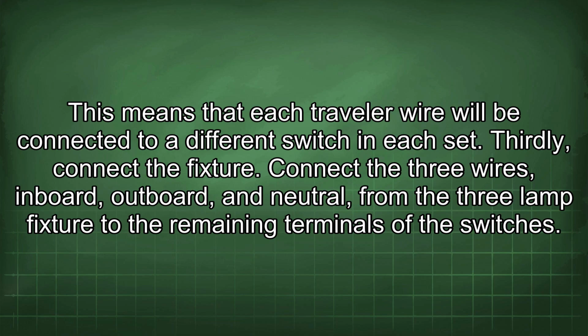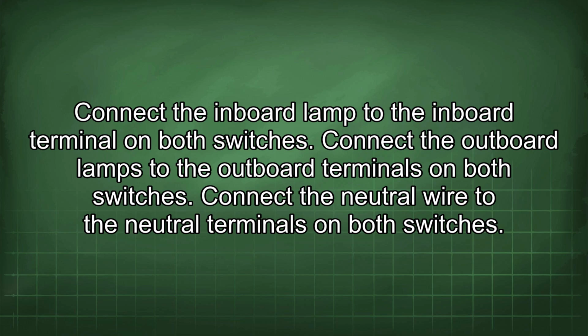Thirdly, connect the fixture. Connect the three wires, inboard, outboard, and neutral, from the 3-lamp fixture to the remaining terminals of the switches. Connect the inboard lamp to the inboard terminal on both switches. Connect the outboard lamps to the outboard terminals on both switches. Connect the neutral wire to the neutral terminals on both switches.